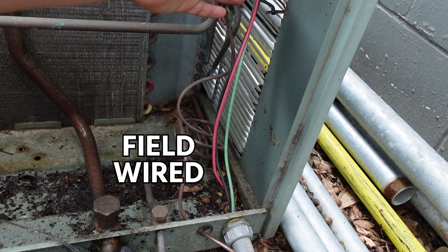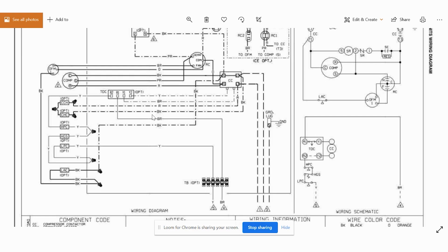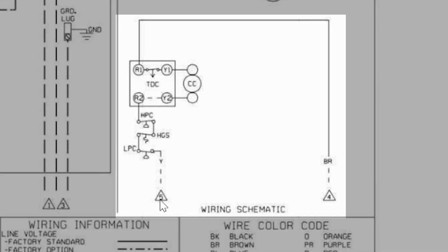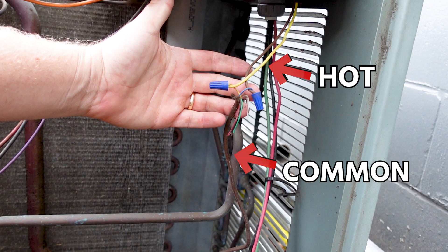So even on a lot of these optional devices, you would have to field wire these in. On the standard side of something that's not optional, you're going to see these two. These are our low voltage. Our low voltage brown, which is our common, and our low voltage Y, which is our hot.